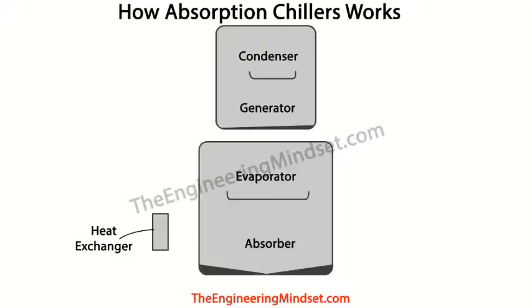Let's look at the main components of it. In the top chamber, we'll always have the condenser and the generator. In the lower half of the chiller, we'll always have the evaporator and the absorber. And then on the side, down below, near the bottom, we'll also have a heat exchanger.